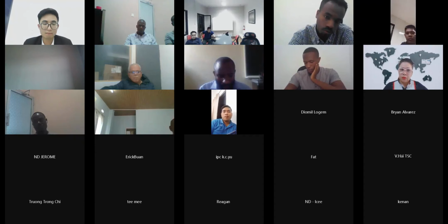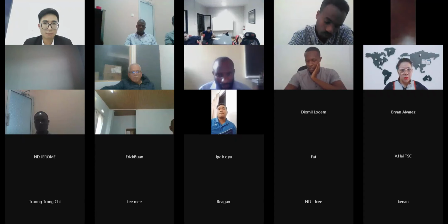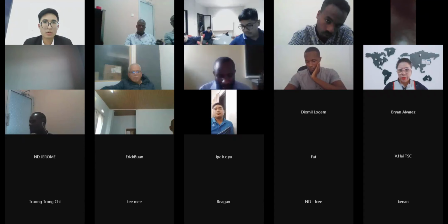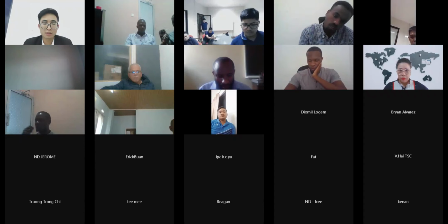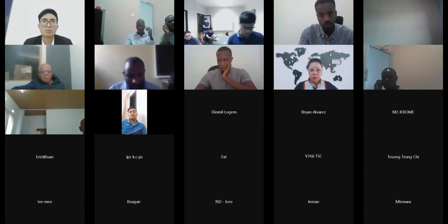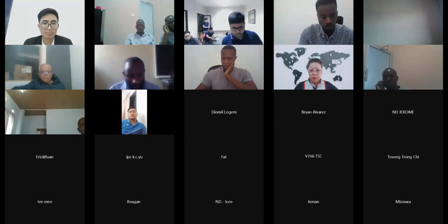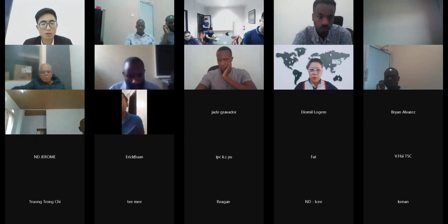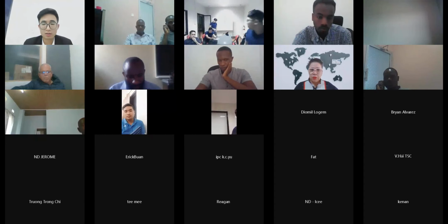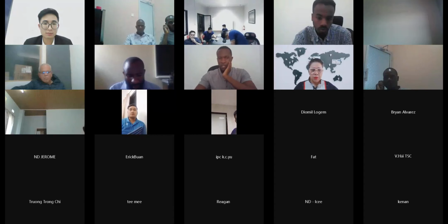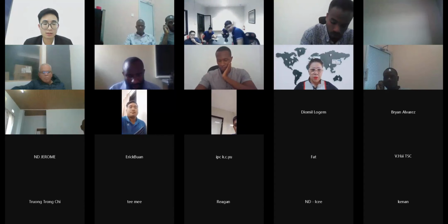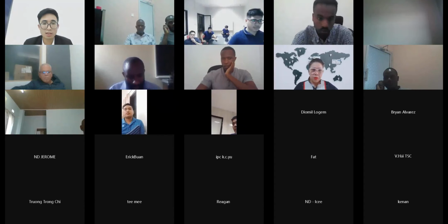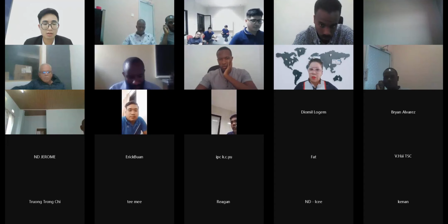One more question about real-time video recording - does the system support real-time video recording? For the 112B, we don't provide that function. But during fluoroscopy you can see a dynamic image, right? You can see the dynamic image, but you won't be able to record it - actually, you can record it. Once your foot is off the step switch, the image shows only one picture, the moment your foot left the switch, so that's a static picture.